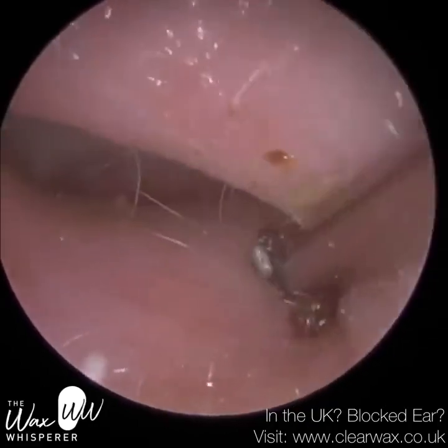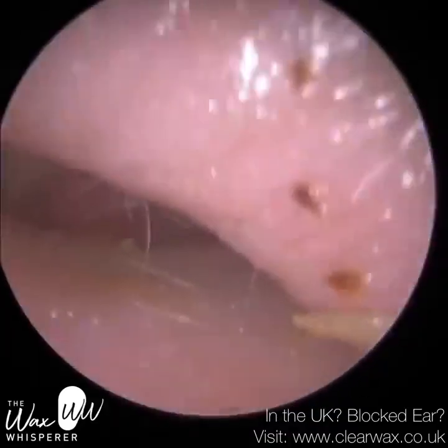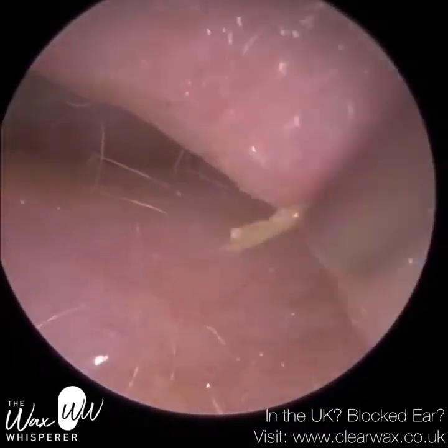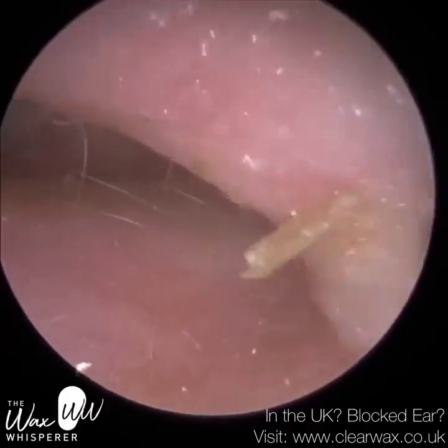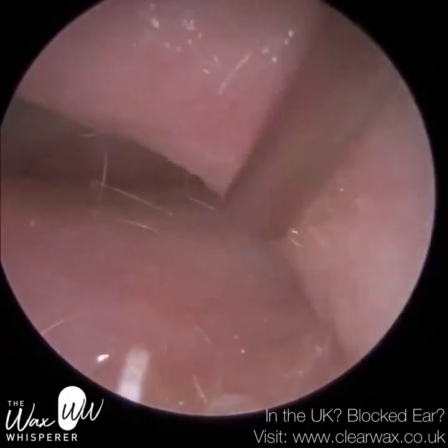So stage one is just to get the instrument in the ear, and you want to position the endoscope just past the first bend, and that's the first bend where I am now, and then to the right, in the case of the left ear, so it's the bottom right-hand side of the ear canal.